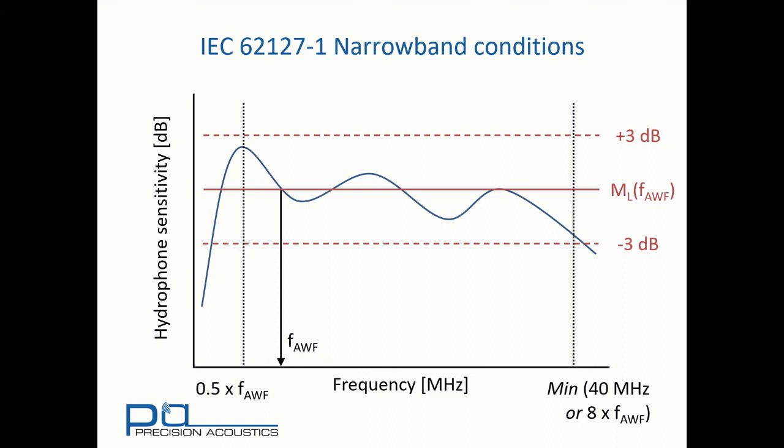This sounds like a lot of work, but let's consider why. If we are able to use the narrowband approximation, we can simply obtain the pressure waveform by dividing the voltage waveform by the sensitivity at the acoustic working frequency.